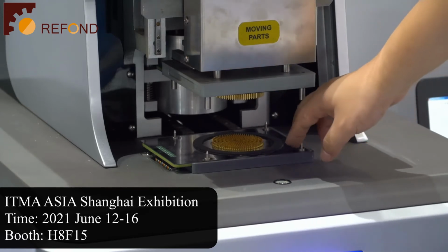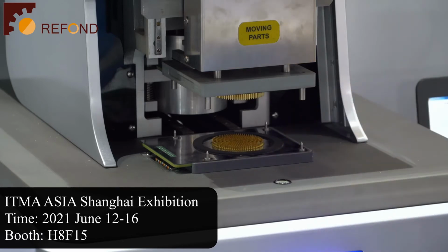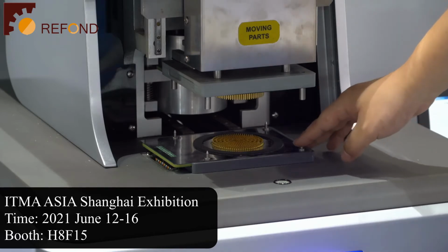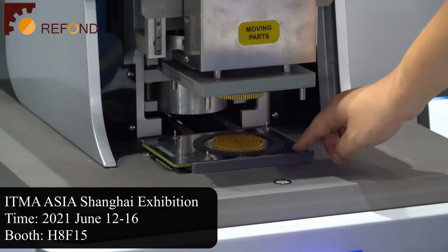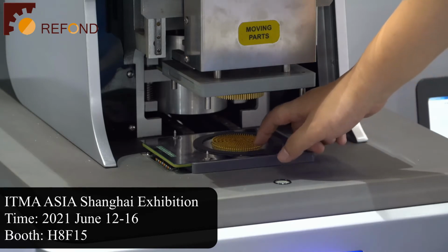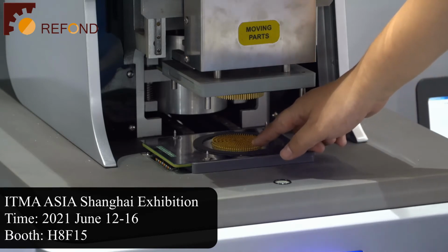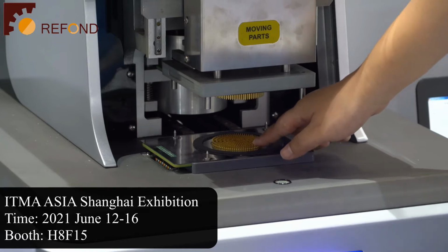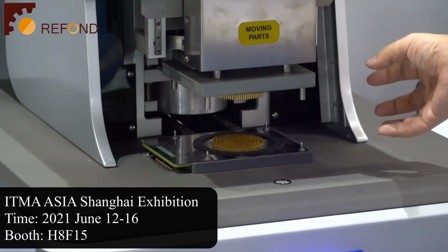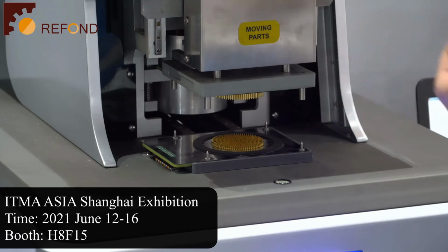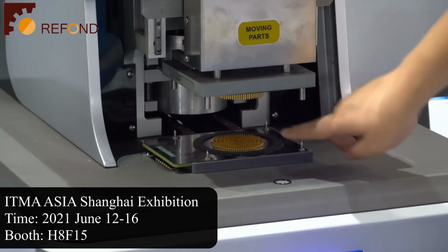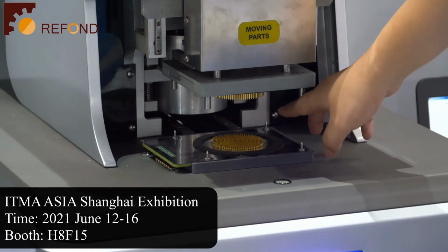Since the test liquid used in this test is salt solution of sodium chloride or calcium chloride, after a lot of tests, there will be some salt crystals on these pins, which may corrode these pins and affect the test measurement in the future. So we also implemented automatic cleaning device for these test probes. Back in the machine there is a cleaning cup.